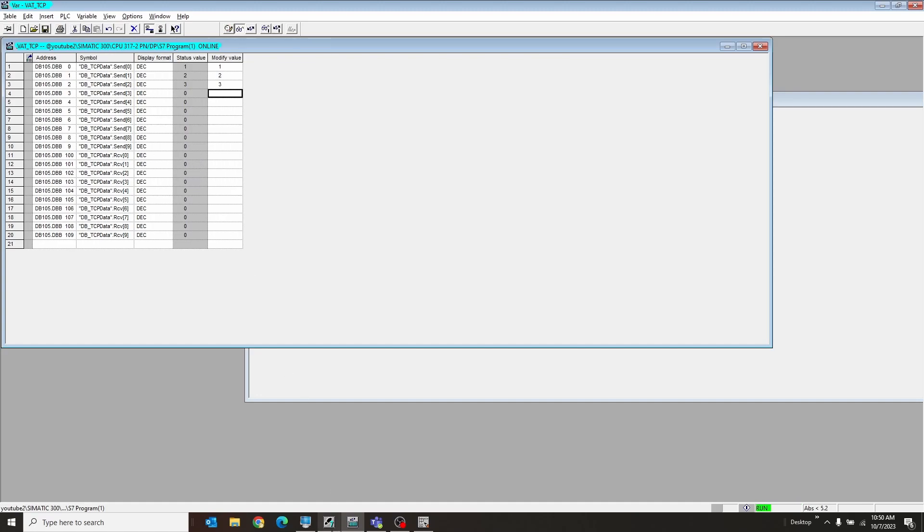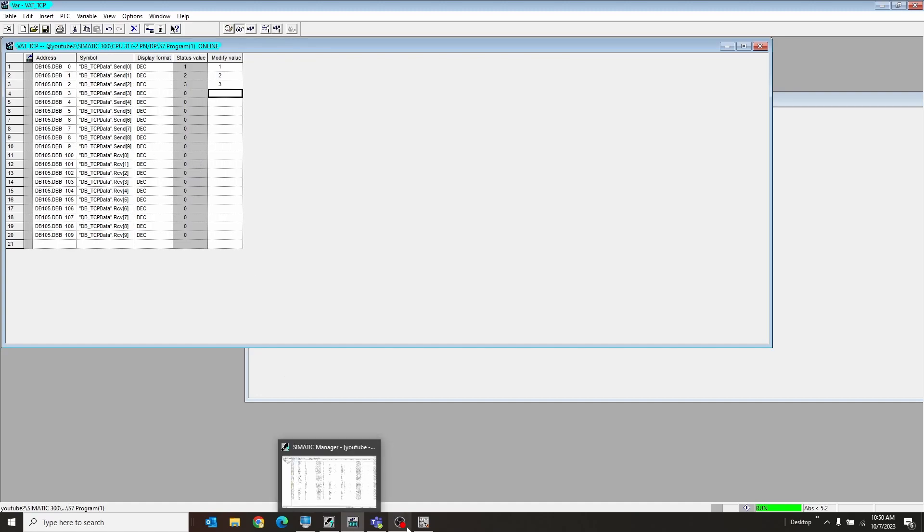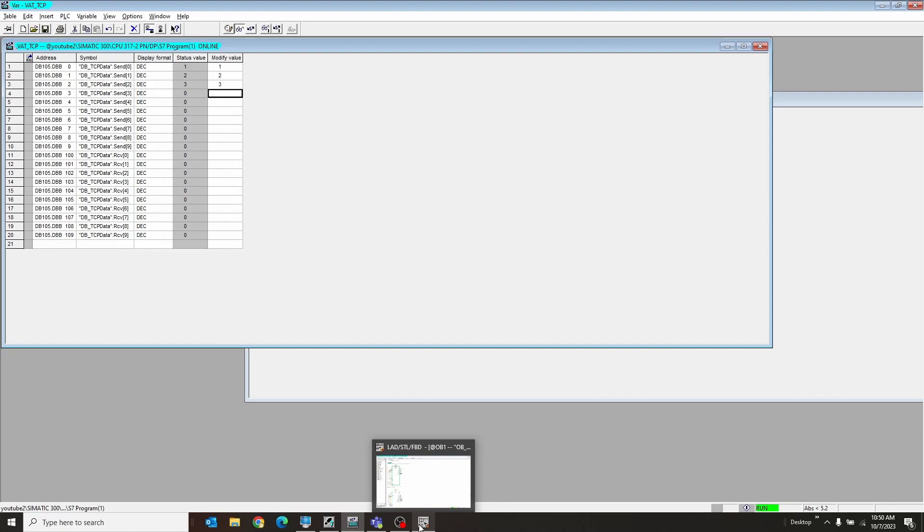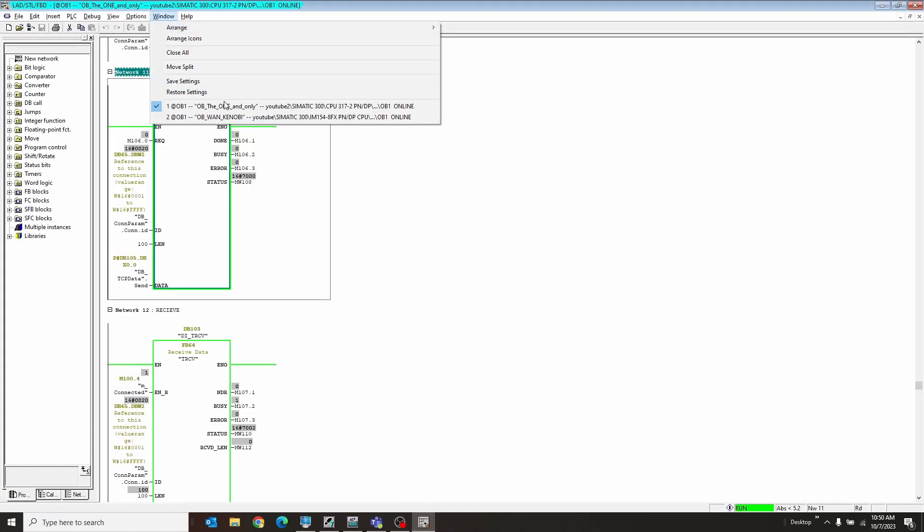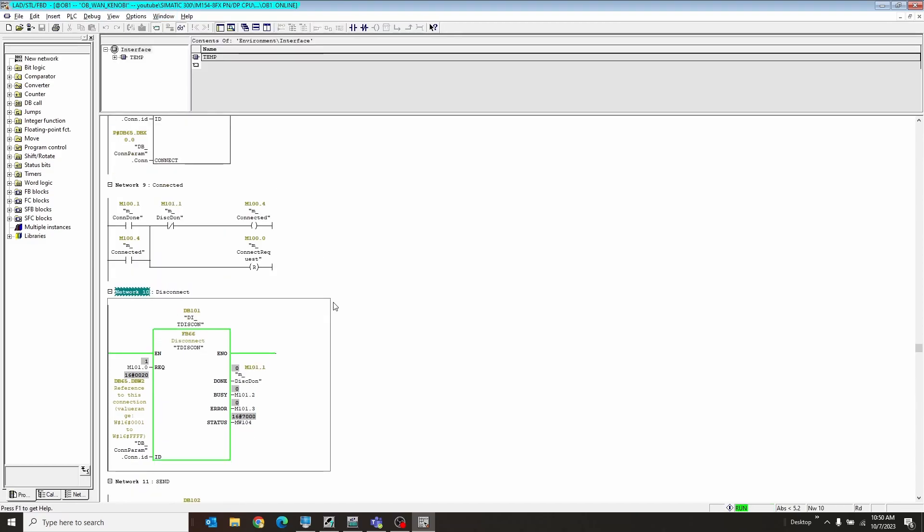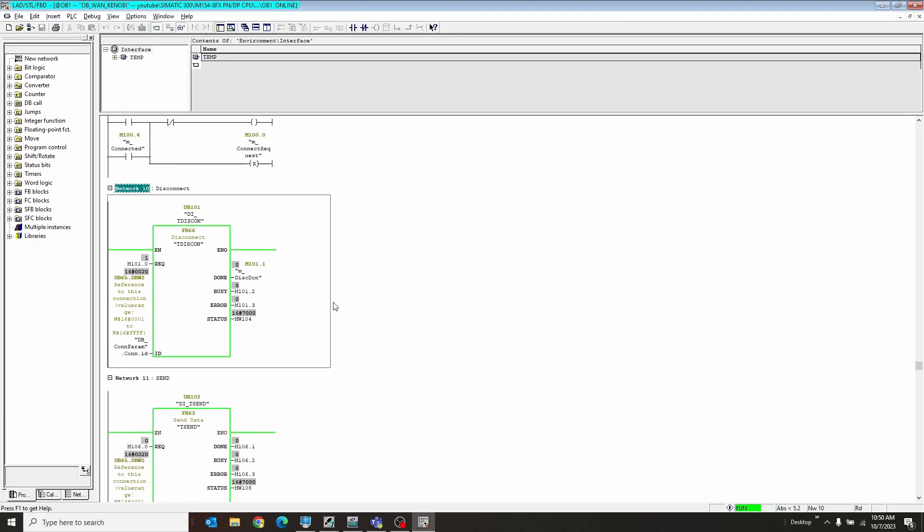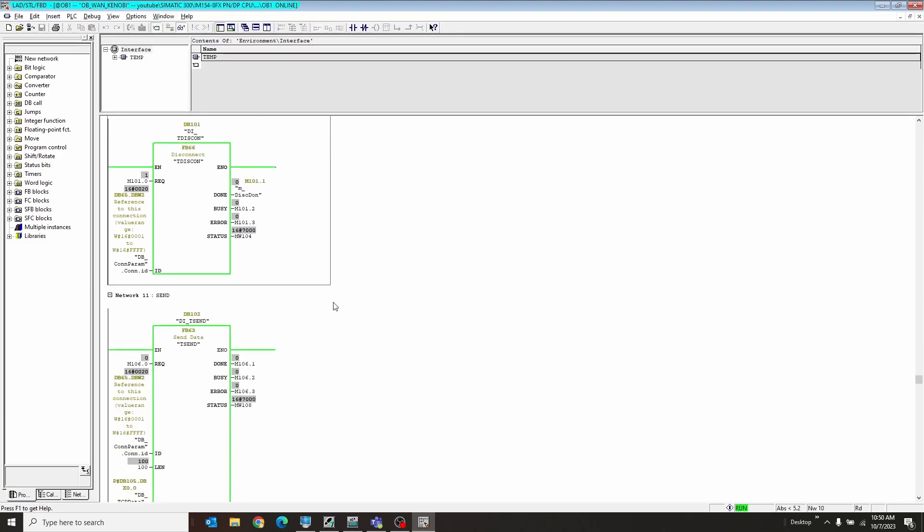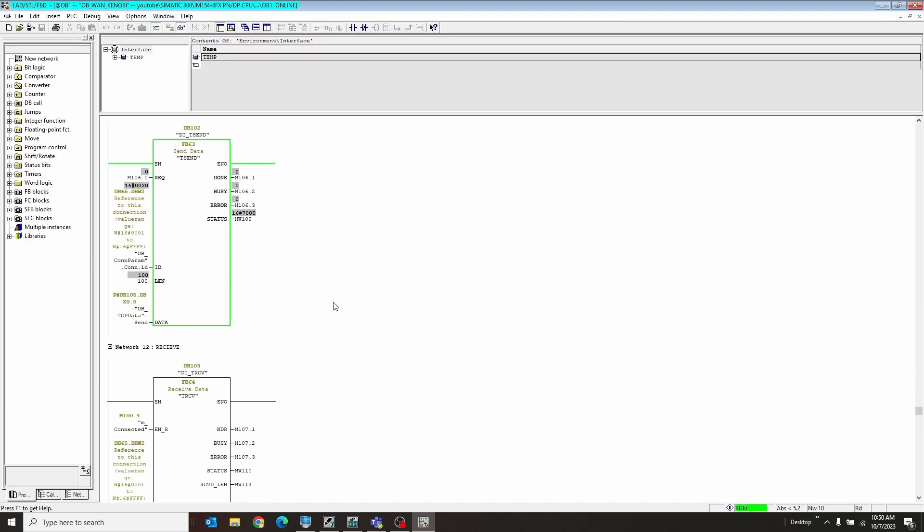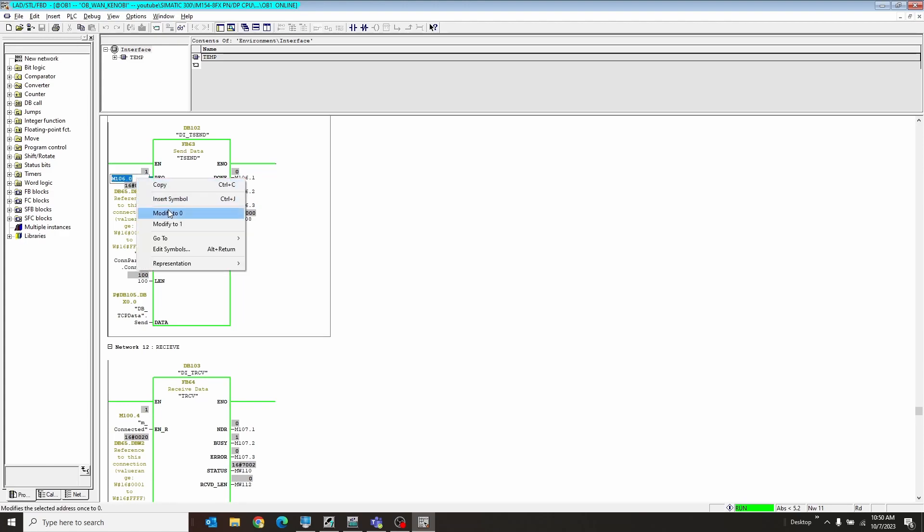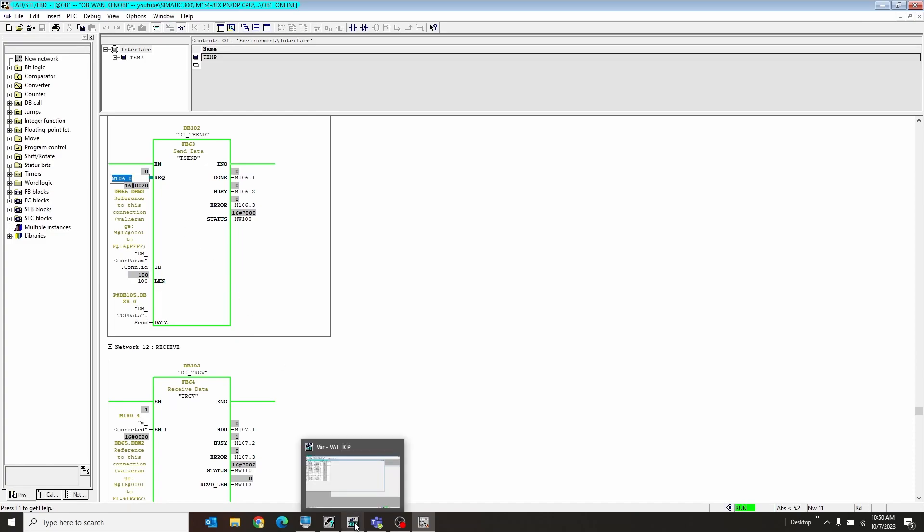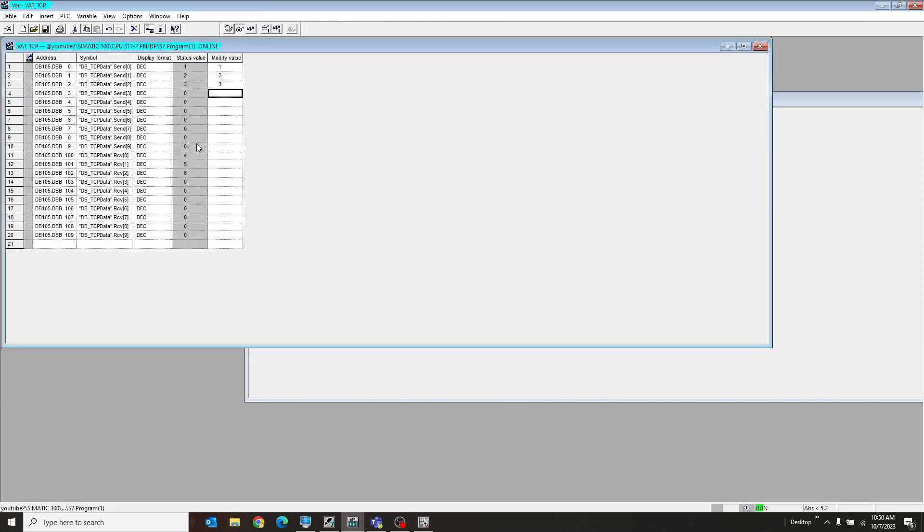And so we're just going to hit send on the second PLC to see that the first PLC has received those three bytes. Actually, it's receiving 100. But in this case, I've only changed three. We're going to go to our second PLC, the one with the inactive connection or the passive connection. We're going to go down to send. We're going to right click this dude. Hit send. We're going to turn our send off. We can go back to our first PLC here. And there he is. The 4, 5, 6 is received on the receive side of the first PLC. And that's it.